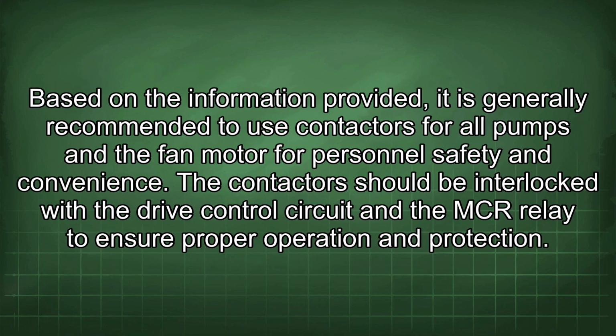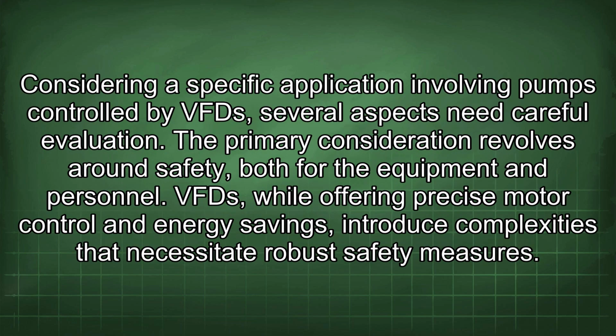Based on the information provided, it is generally recommended to use contactors for all pumps and the fan motor for personnel safety and convenience. The contactors should be interlocked with the drive control circuit and the MCR relay to ensure proper operation and protection. Considering a specific application involving pumps controlled by a VFD, several aspects need careful evaluation. The primary consideration revolves around safety, both for the equipment and personnel. VFDs, while offering precise motor control and energy savings, introduce complexities that necessitate robust safety measures.